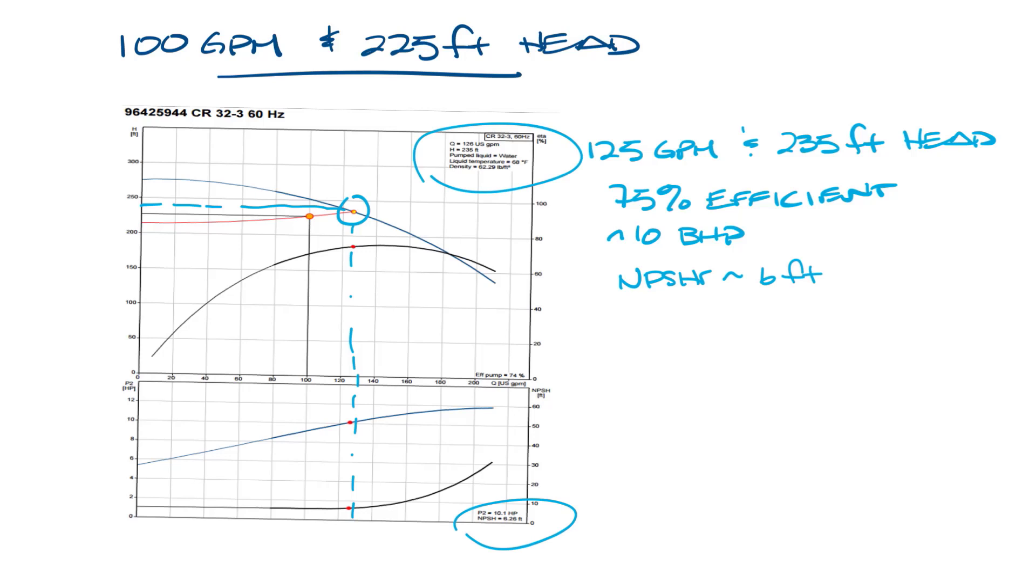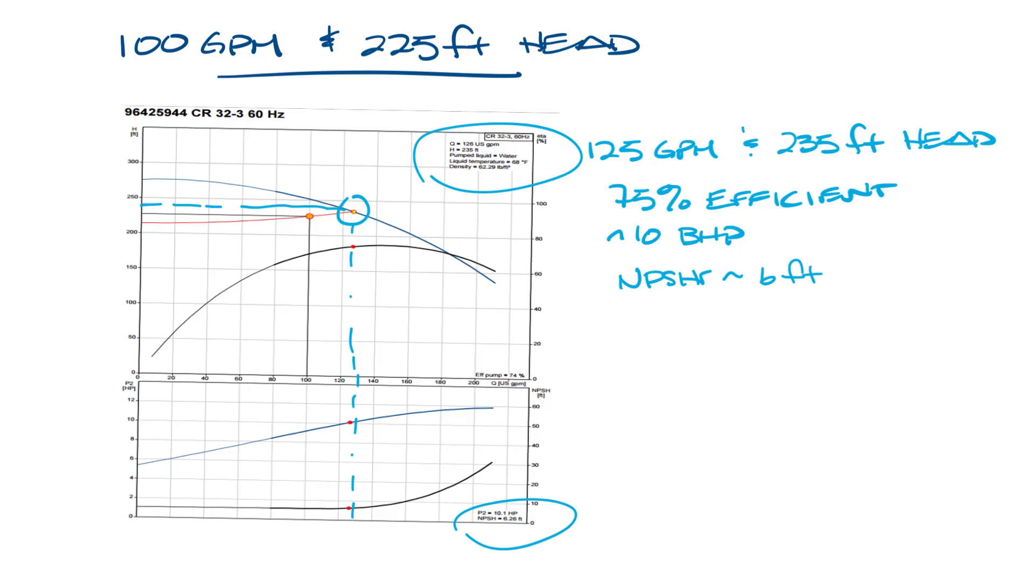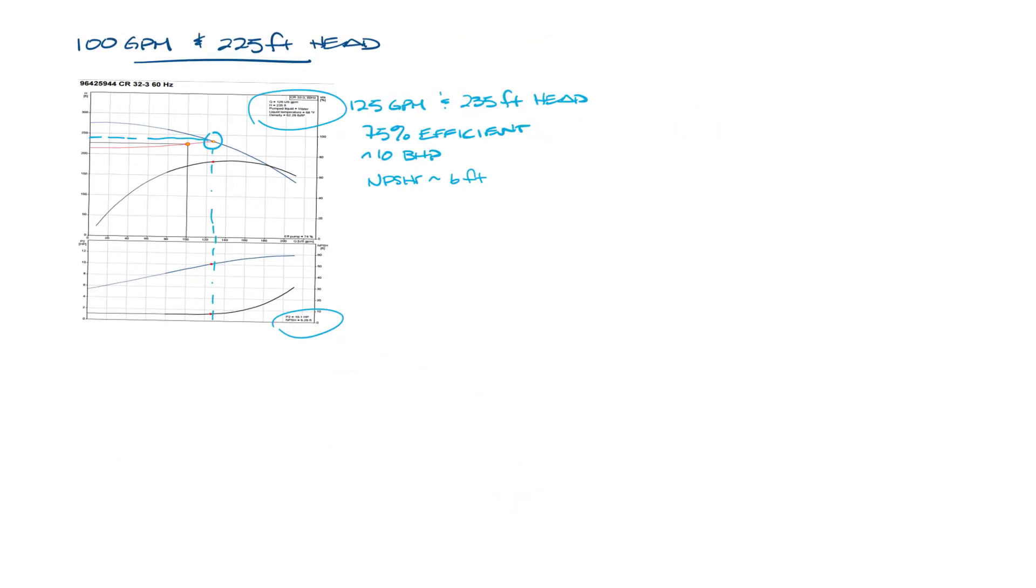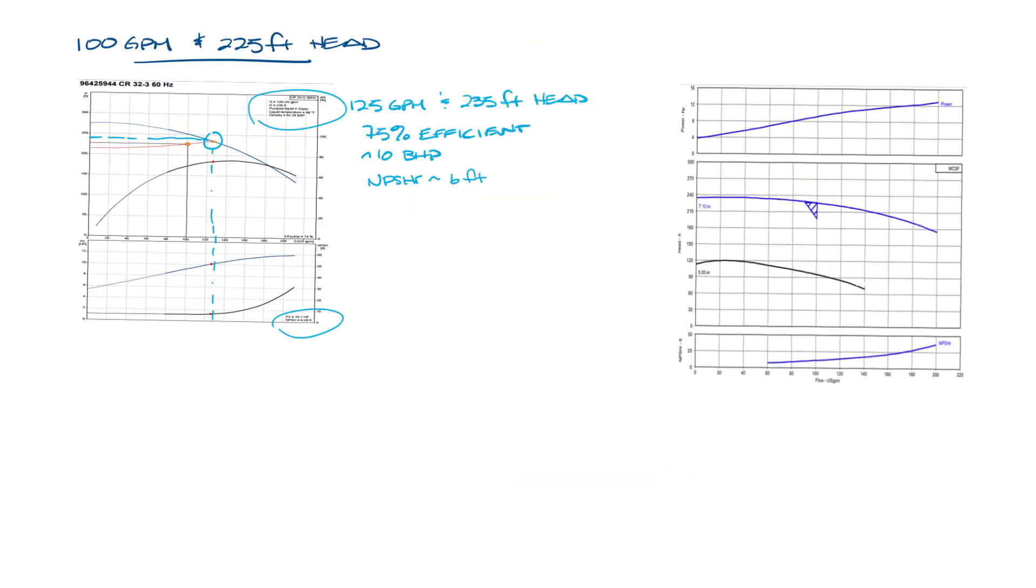But a single pump isn't the only pump that can meet our design requirements. Let's pull up another pump curve. This pump also meets our requirements. In fact, the 7.1 inch impeller will give us our exact performance of 100 GPM and 225 feet of head.